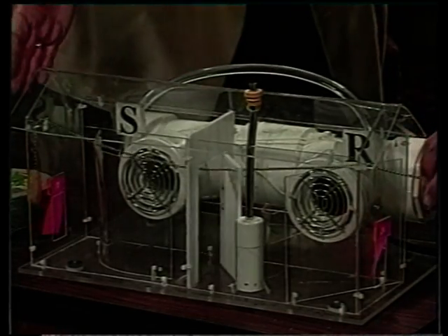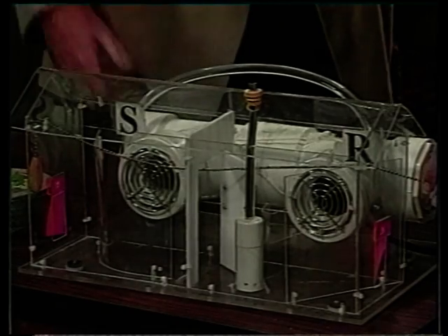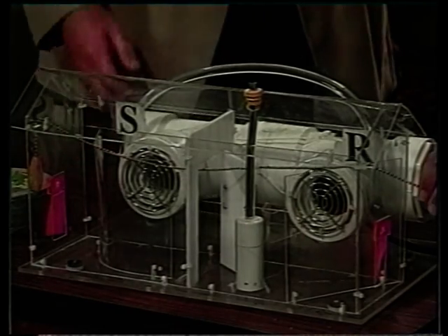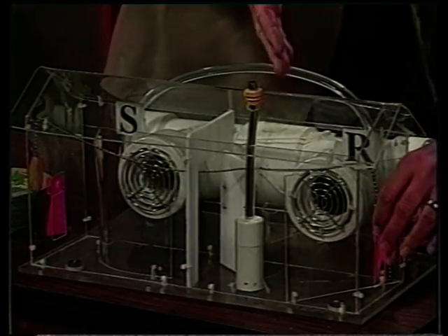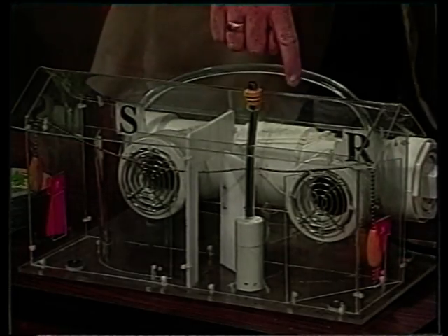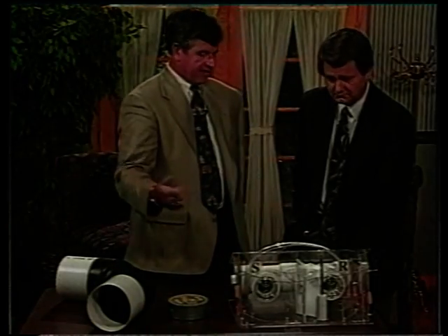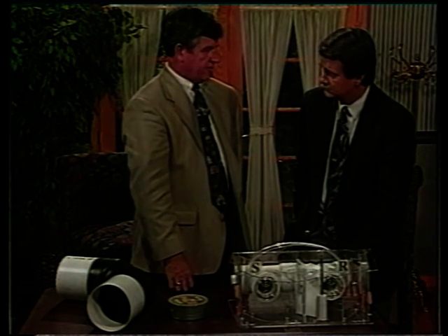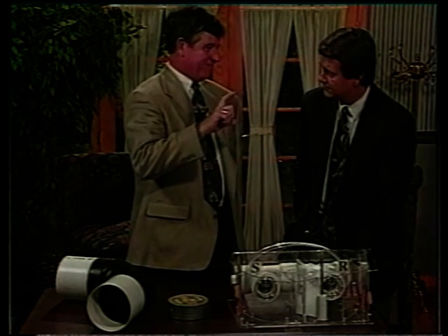Open the door again. Watch. Now the house is in total balance, and it's no problem. See, if you put say 200 CFM, cubic feet a minute of air into a room, you've got to be able to let that air get out to get back to the return air. So you need to cut 3 or 4 inches off the bottom of your door.